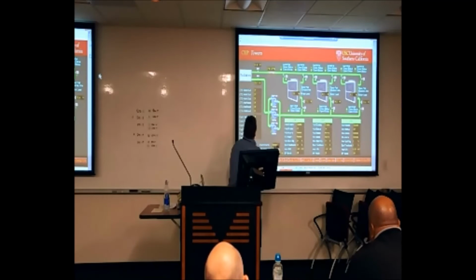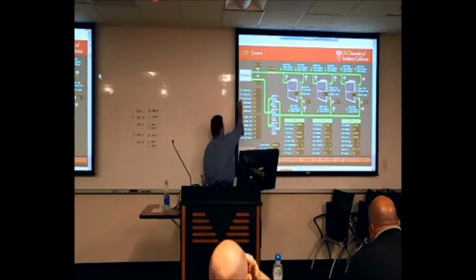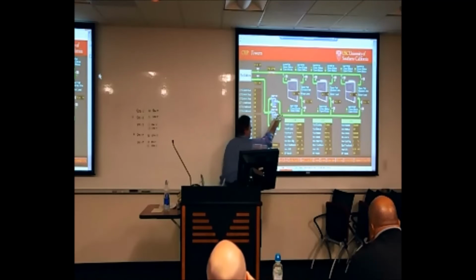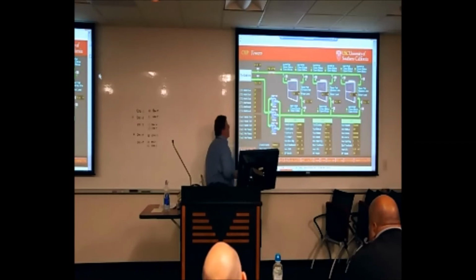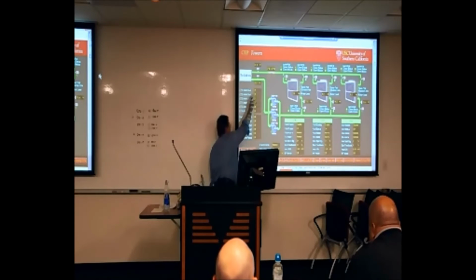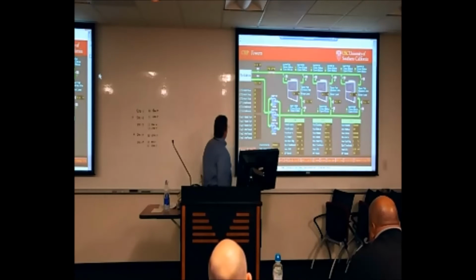And all of those tower failures need to be reset the same way the pumps need to be reset. So once failed, someone would have to go out and fix the problem that caused it to fail, and then the alarm reset would have to be toggled to on to reset the tower and bring it back into its sequence. And again, that's just a flip to on. You can leave it on or you can turn it off, but it's always on a flip to on that the reset is going to occur.